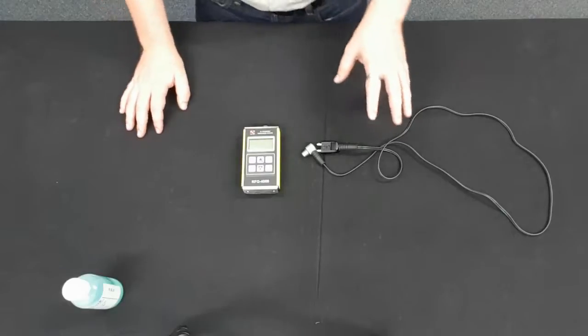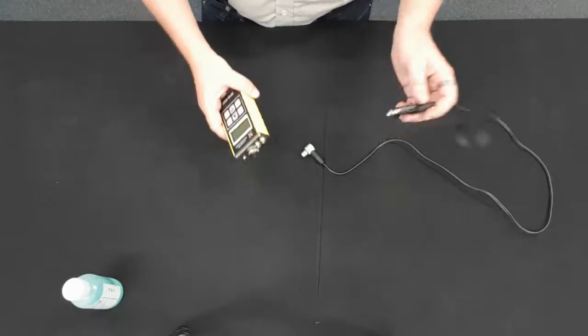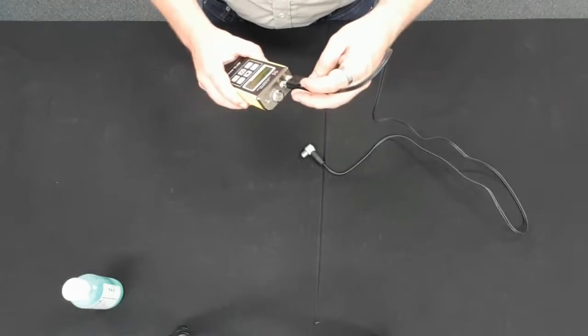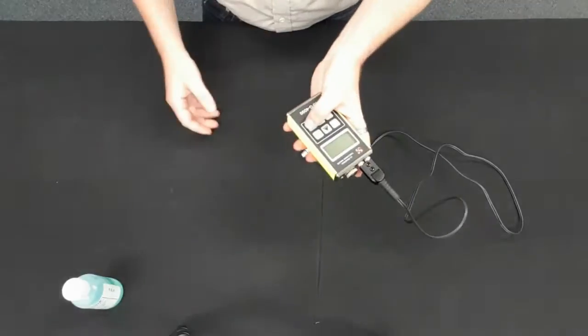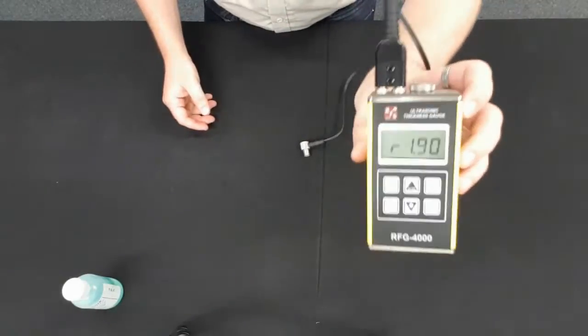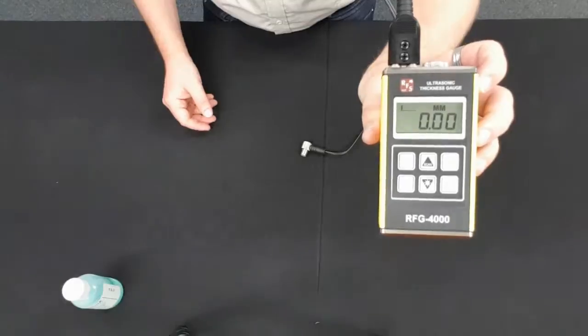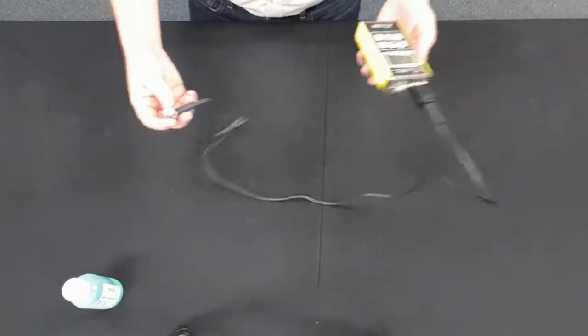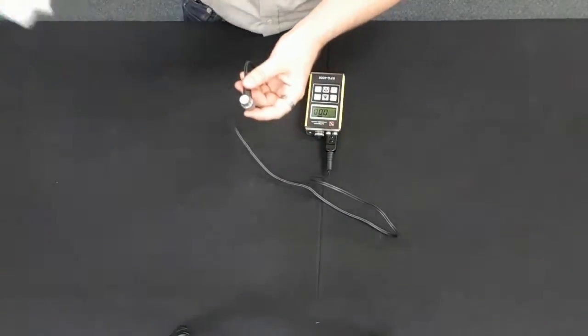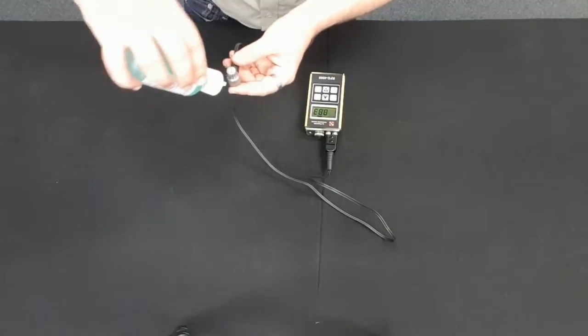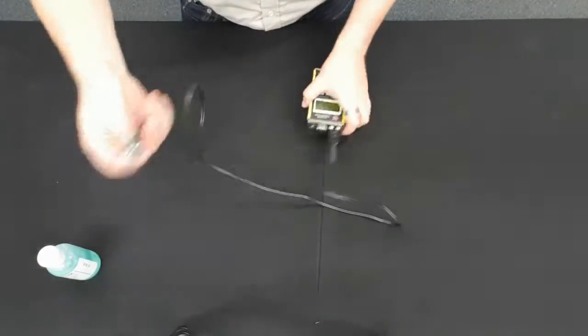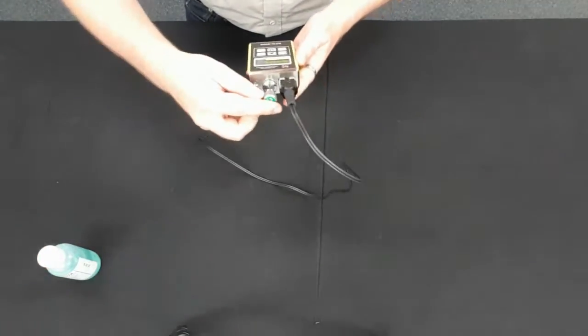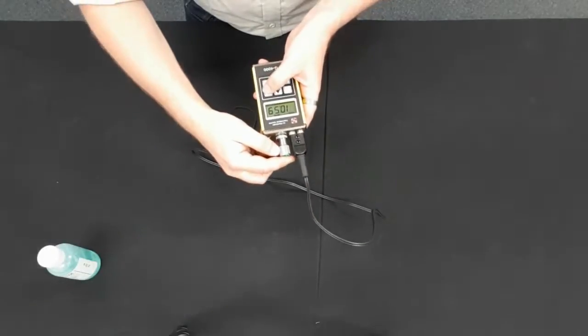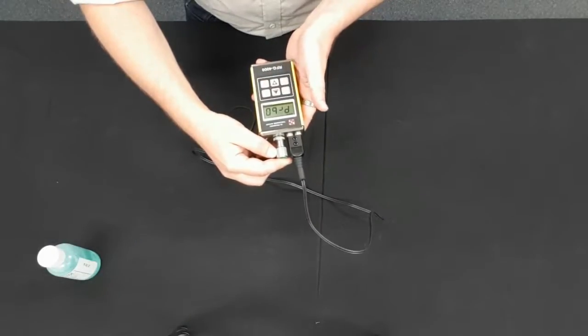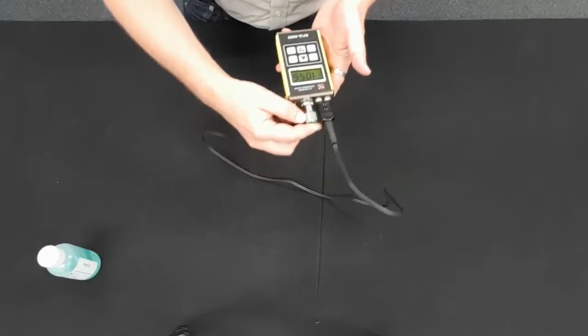So using the gauge is very simple. Turn it on, plug the probe in, doesn't matter which way it goes in, and just power on. See, it's a nice big display, it makes everything very clear. First thing you need to do is a probe zero, so I just need a little bit of couplant on this. So just push the probe against the probe zero block on the top here. Press probe zero. That is calculating the delay in the probe.